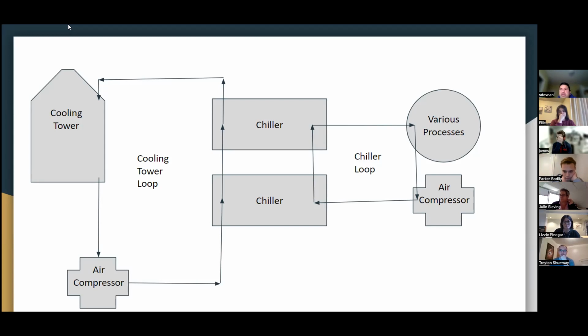Oh, okay. The reason I brought that up is chilled water is water. It starts to freeze at 32, as you all know. And typically chillers will turn off at 39 degrees for freeze protection, because that is too cold. But there are ice rinks and other facilities that are designed to be below 32 degrees. And in that case, they put in glycol, antifreeze, right? That's all there is to it. And that allows you to chill that fluid to below 20 degrees and still maintain it in fluid media.